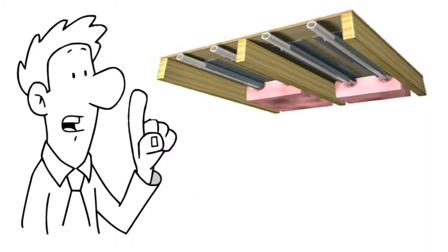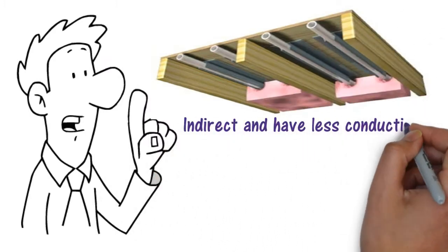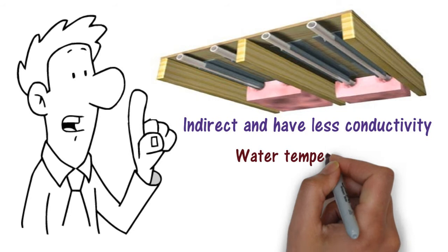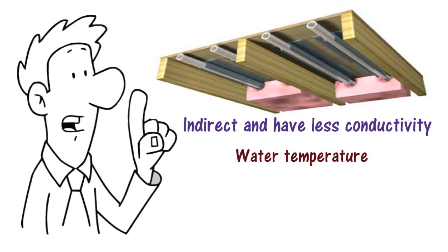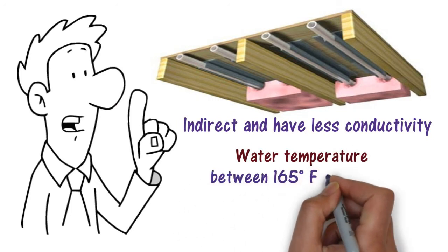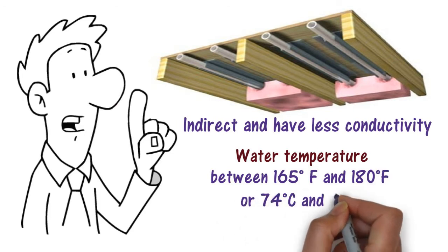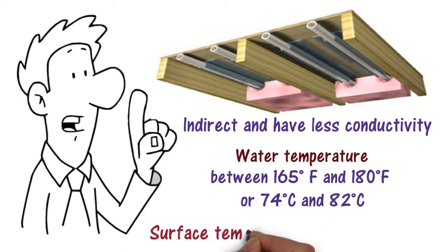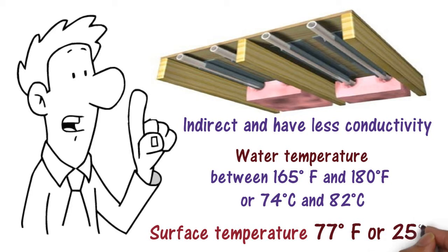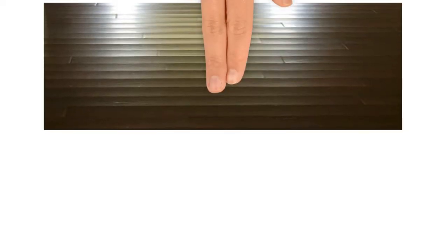Under-joist heating systems are not as direct and have less conductivity. The area being heated is larger, which requires water entering the system to be 165 degrees Fahrenheit to 180 degrees Fahrenheit to achieve the same 77 degrees Fahrenheit maximum surface temperature. The higher temperatures can cause issues with the engineered or solid hardwood flooring.